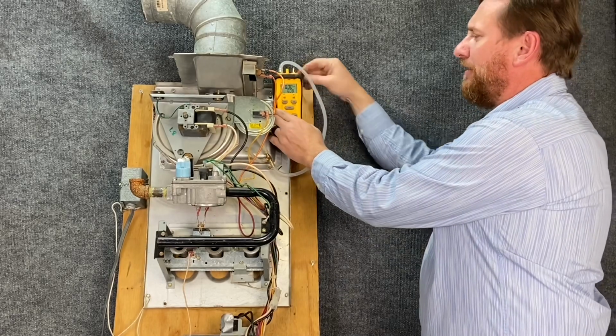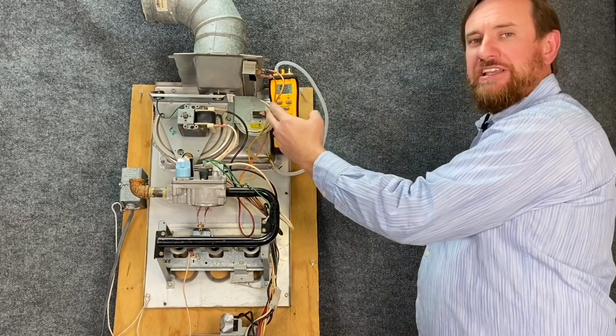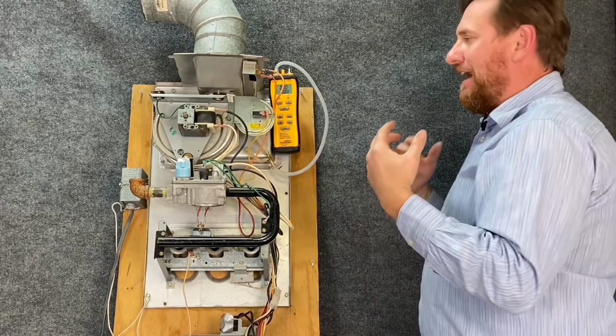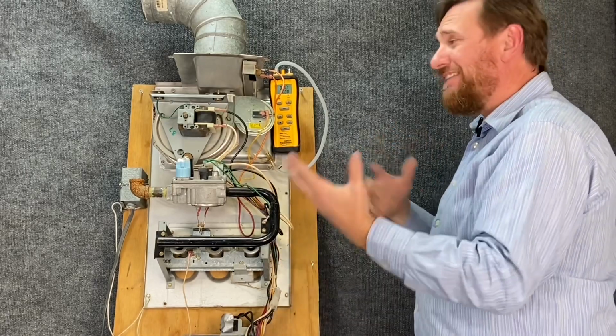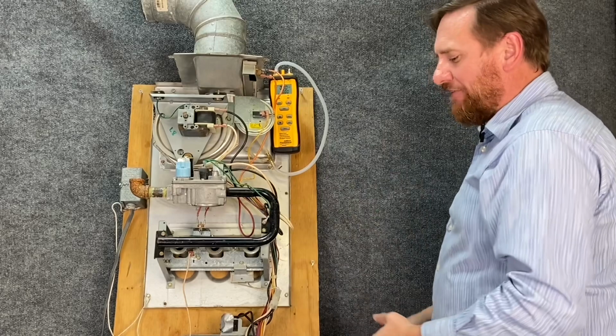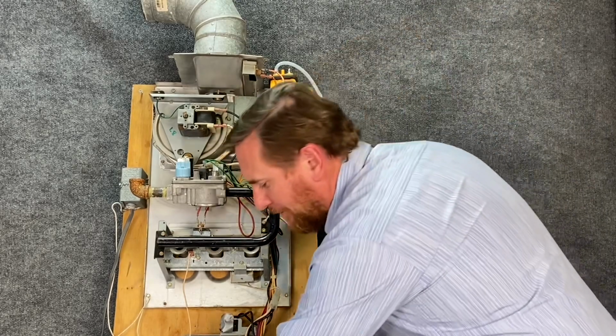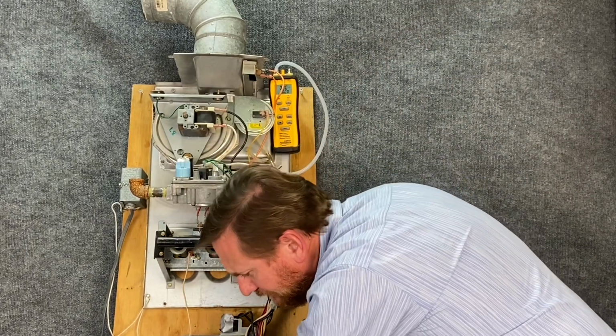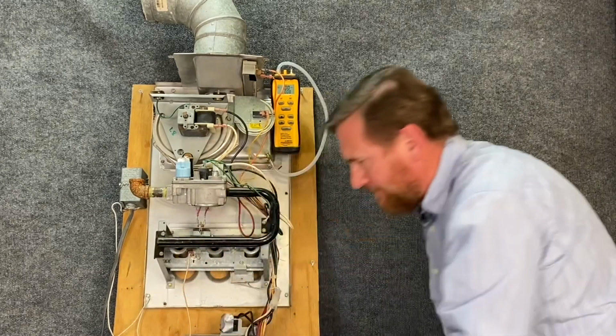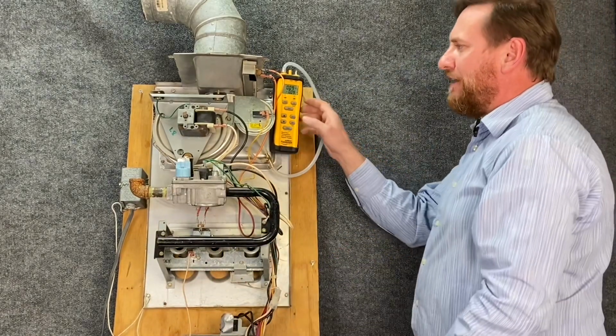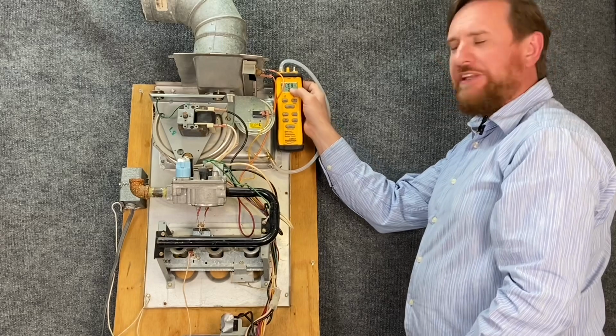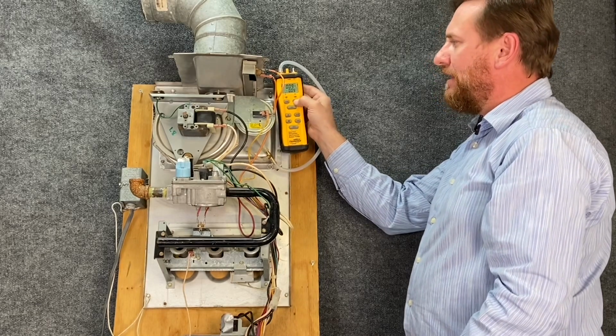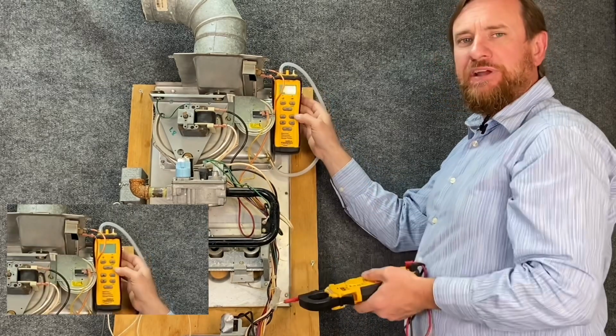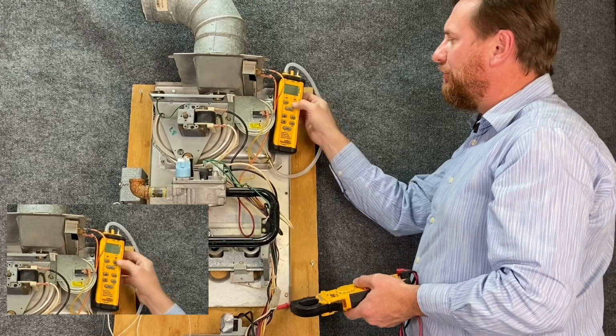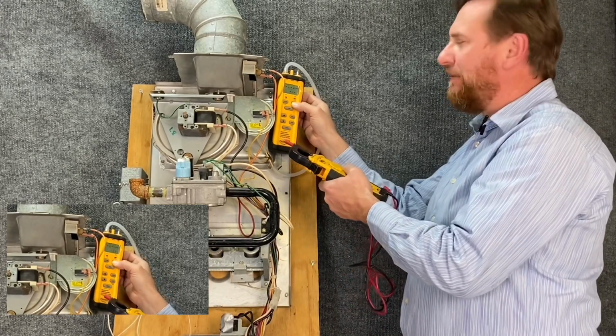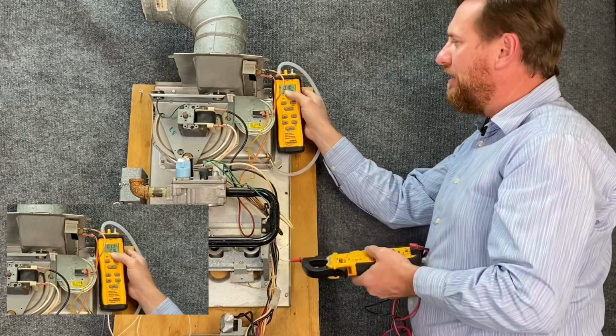So what we're going to start with is, is the switch good? Is it bad? Are we getting enough vacuum? My control board, the switch, is it closing? What's happening? Let's find out. We're going to have a call for heat and go through our sequence of operation. Now our inducer fan motor is working, but we're pulling 0.1 inches of water column. This switch is rated at 0.25 inches of water column.